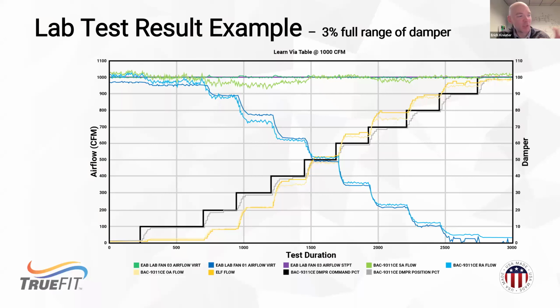So it's a little bit of an eye chart, but you can see, again, as expected, as we step that damper up, our supply stays fairly steady, our OA goes down, our return goes up, and they always add up to the proper total supply because of the nature of our measurement.